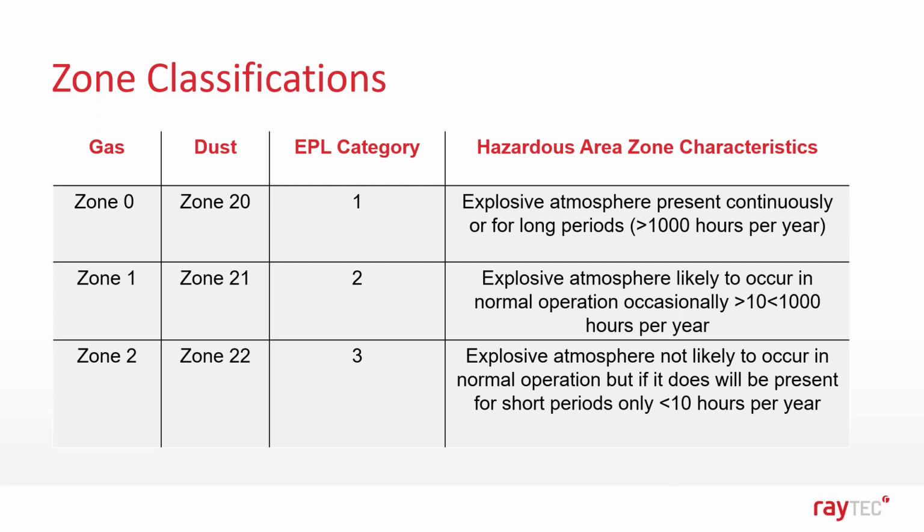And in terms of their probability of occurring, explosive atmospheres are present continuously or for long periods. So in zone 0 applications, typically the explosive atmosphere will be present for more than 1,000 hours per year.